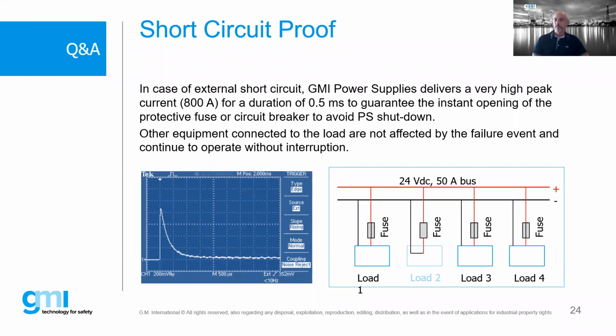So this peak will be delivered exactly to the load that is causing the short. This will open the fuse or the circuit breaker for that load, and so the other equipment connected to the power is maintained without the system or the other loads being affected by the short circuit you got on this kind of load. So this is another special feature.